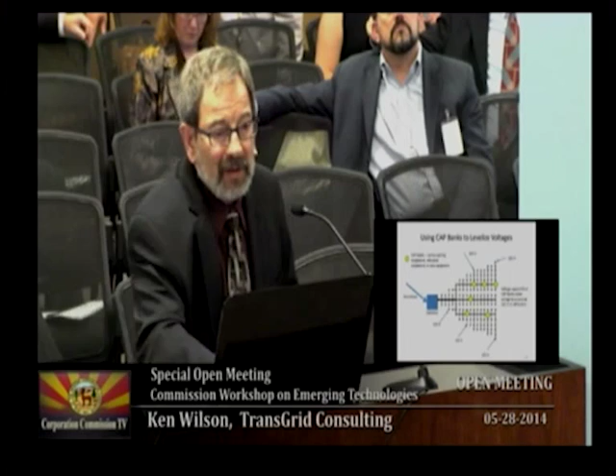Today, the utility uses capacitor banks for power quality, but what we want to do for CVR is to use capacitor banks, and we may have to add some capacitor banks, we may have to move some around for CVR, but what we want to do is to levelize the voltage down all of the paths of the feeder. And what I'm showing here is just an example. We're putting capacitor banks out on the grid to bring all of the voltages up to, say, 125 volts. And this is just an example.